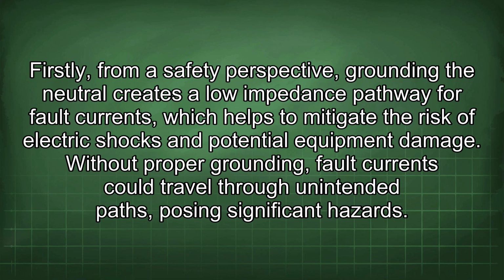Firstly, from a safety perspective, grounding the neutral creates a low impedance pathway for fault currents, which helps to mitigate the risk of electric shocks and potential equipment damage. Without proper grounding, fault currents could travel through unintended paths, posing significant hazards.